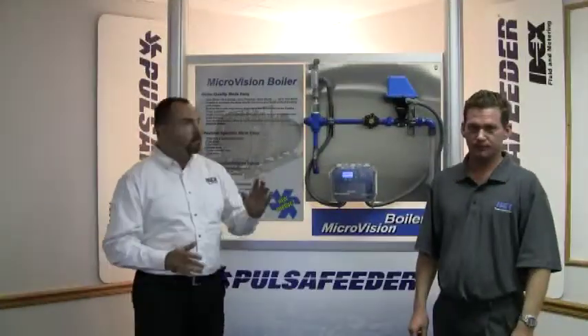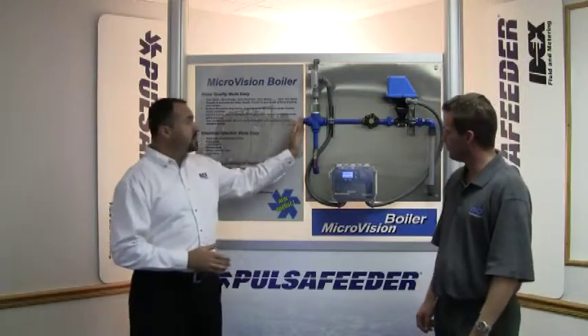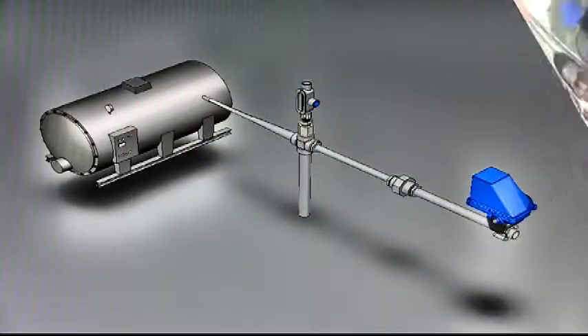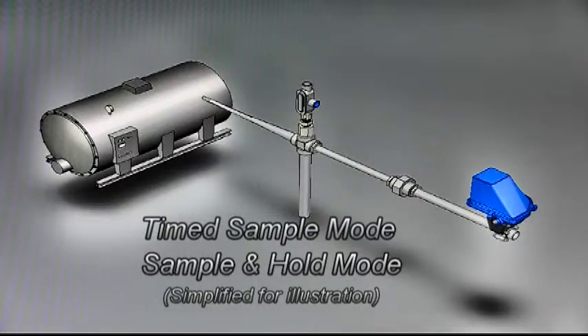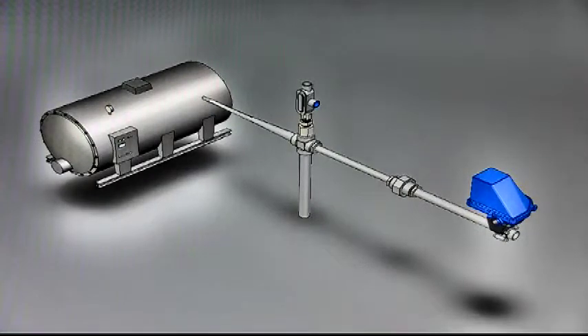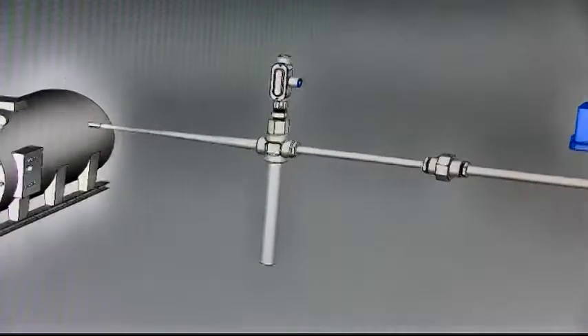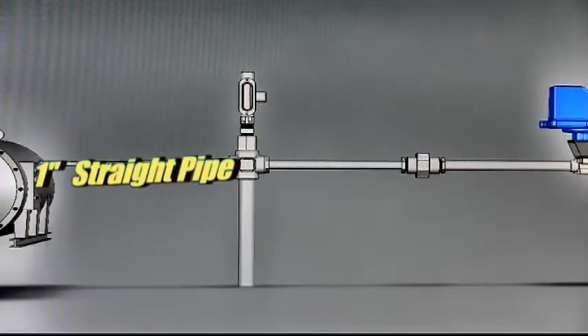The proper installation of the probe is important to reduce steam flash. Steam flash can affect the longevity of the probe's life, in addition to affecting the accuracy of conductivity readings. Proper installation of the probe is essential to reduce steam flash. Install the skimmer line approximately 6 inches below the water level in the boiler. Then run approximately 2 to 4 feet of 1-inch pipe to the cross inlet side.